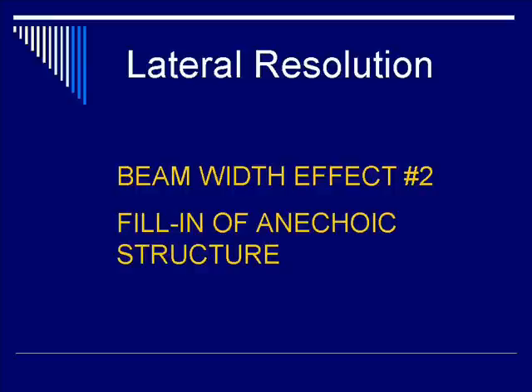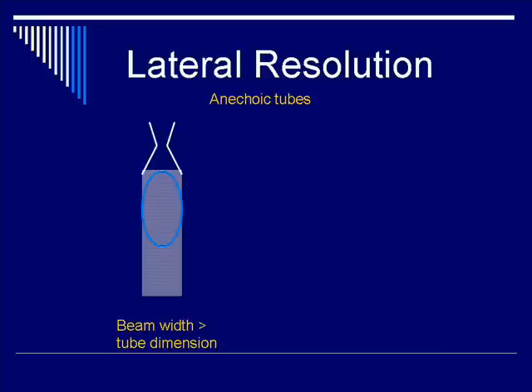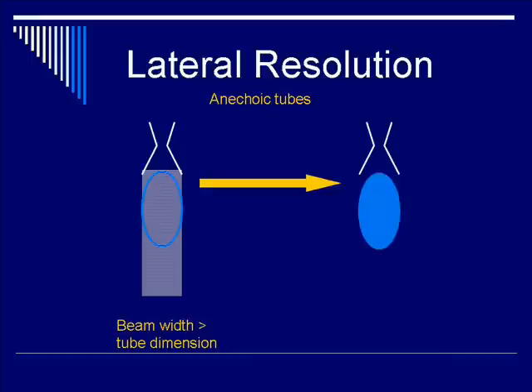The second beam effect to remember is fill-in of an anechoic structure. Anechoic structures could be a cyst — such as a cyst in the liver. However, if the dimension of the cyst is less than the beam width, such that from edge to edge it cannot be resolved in the lateral direction, what we'll have on the ultrasound screen is that the anechoic structure — which is dark within a cystic boundary — will appear as filled in because of the lack of lateral resolution. Hence, fill-in defect. The signal within the cystic structure, originally anechoic or black, will become hyperechoic, which is equivalent to fill-in.